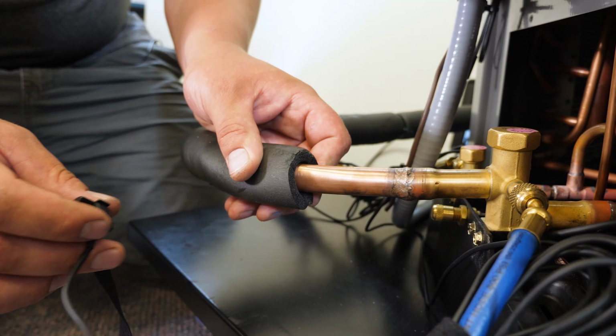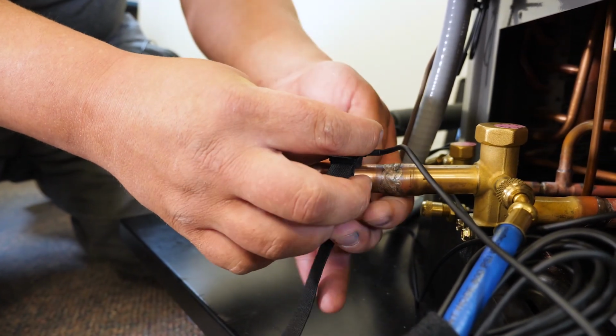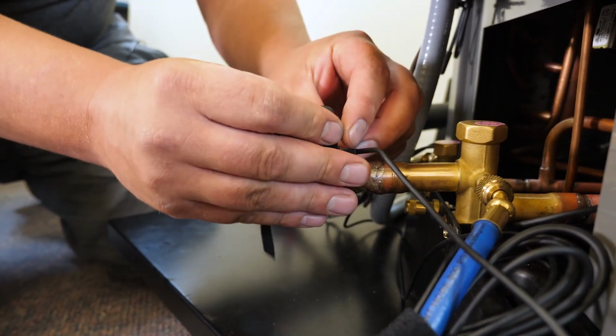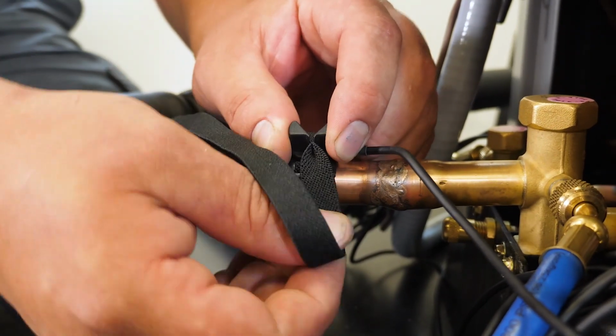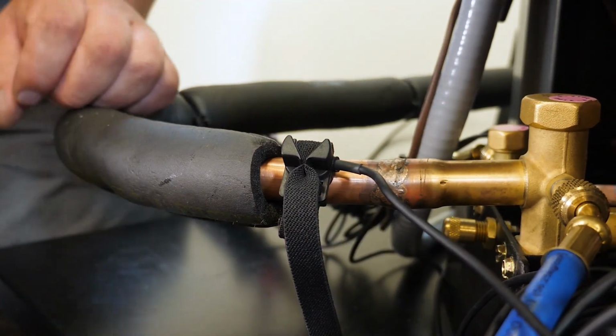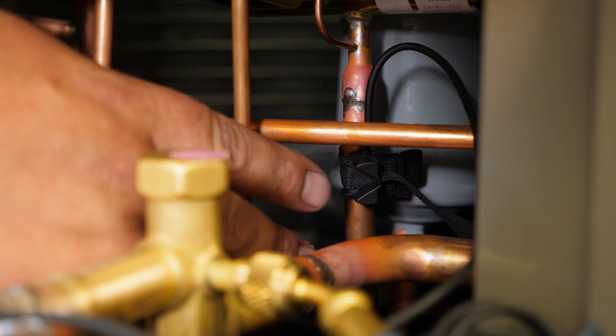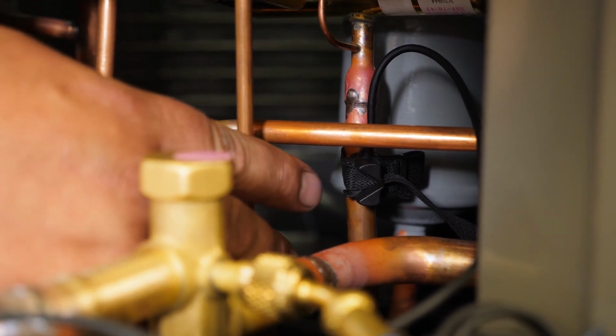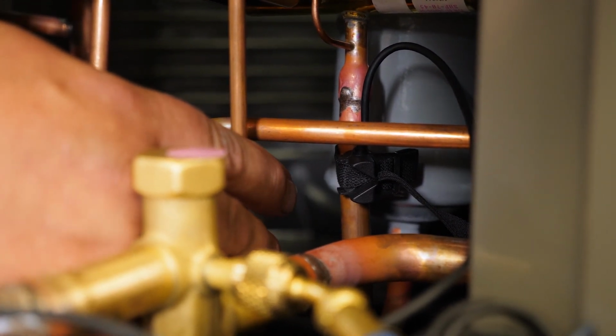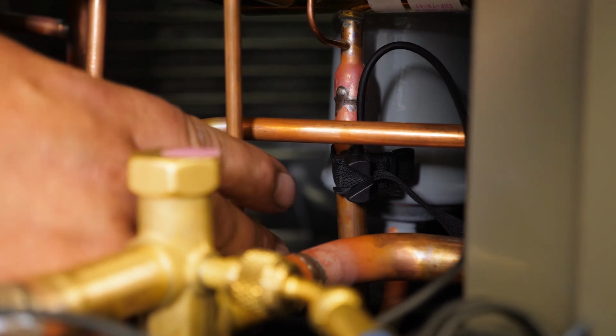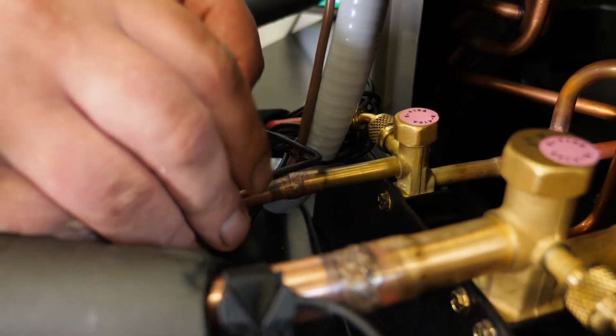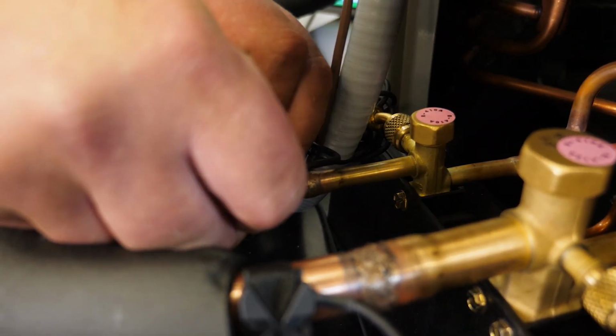So here I'm going to pull back the pipe insulation just a little bit, just enough room to attach my thermistor. Secure that. Okay, so I've already attached my discharge line temperature sensor to the discharge line. That's in my T2 port of my high pressure probe. In my T1 port, I'll connect to the liquid line just past the service valve.